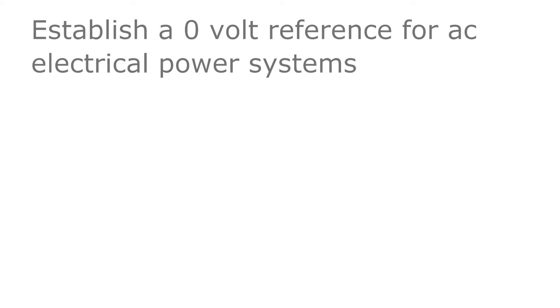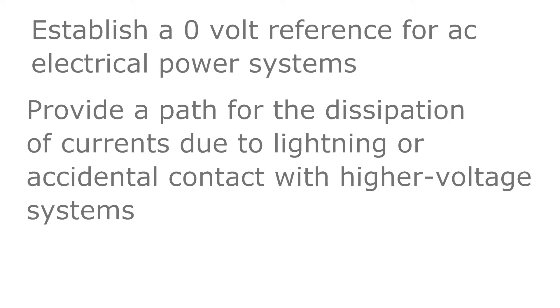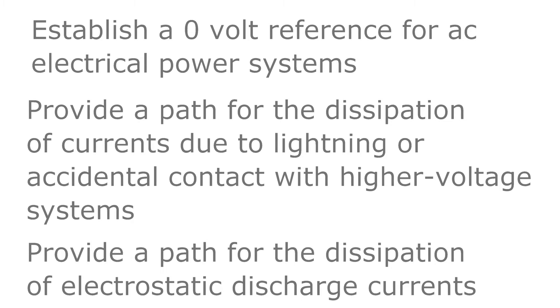Even though you, as an RCDD, may have no authority over the grounding electrode system, it is a critical component for your telecommunications bonding infrastructure. The purpose of the AC grounding electrode system is to: one, establish a zero-volt reference for an AC electrical power system; two, provide a path for the dissipation of currents due to lightning or accidental contact with higher voltage systems; and three, provide a path for the dissipation of electrostatic discharge currents.